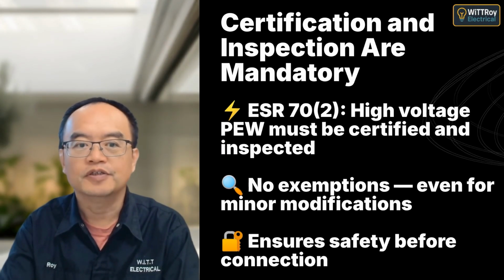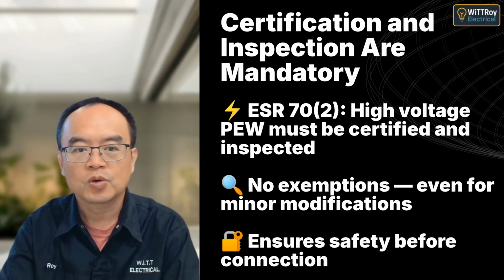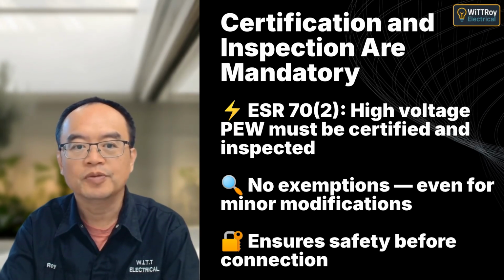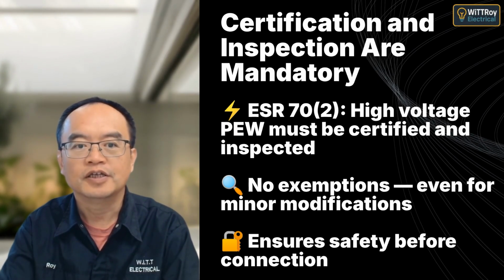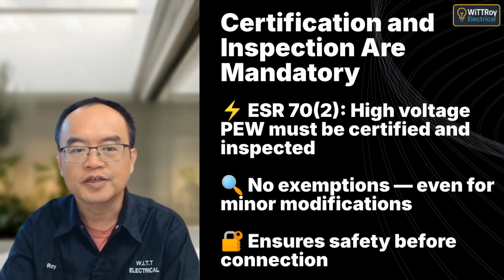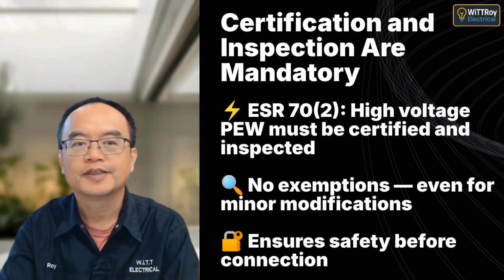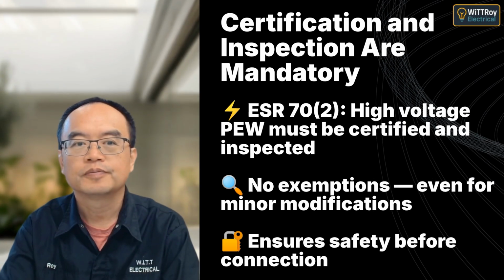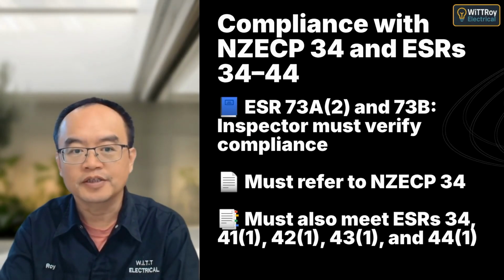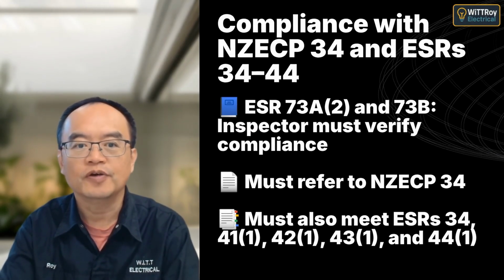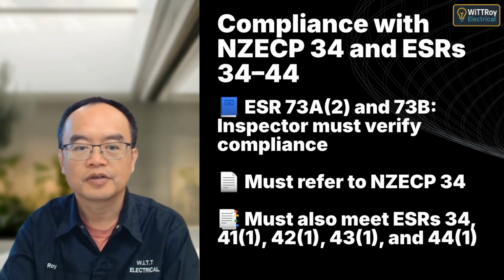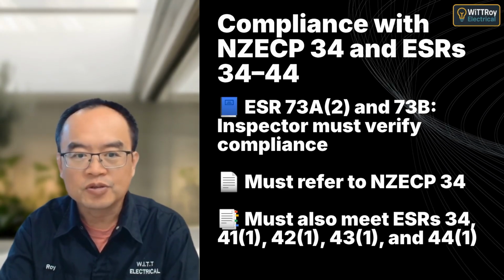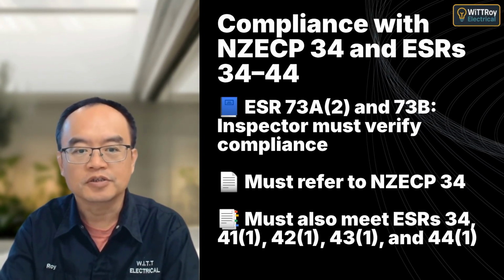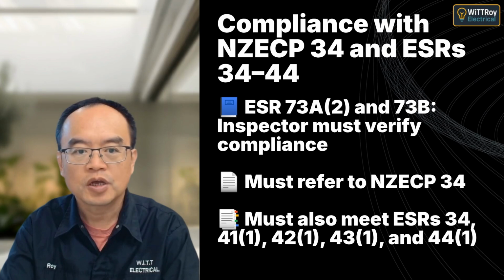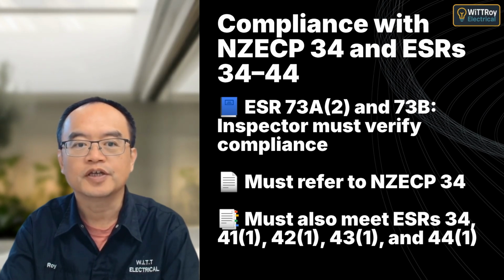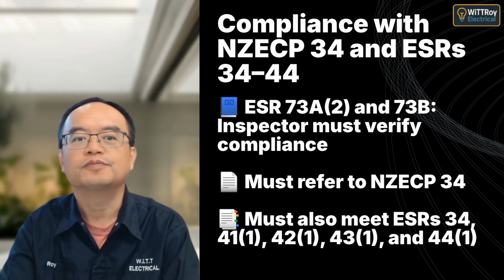Under ESR 70(2), any prescribed electrical work on high voltage installations must be certified and inspected. This applies to all voltages above 1000 VAC or 1500 VDC. When inspecting high voltage installations, you must verify compliance with both NZECP 34 and key high voltage regulations, ESRs 34 and 41 through 44, to ensure work is done safely and meets legal requirements.